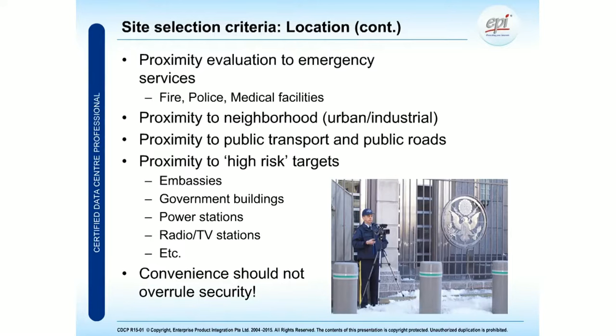Site selection is key. Also, proximity evaluation to emergency services. Should we be installing a data center next to a fire station, for example, or next to a medical facility? That could mean trouble as well. Proximity to the neighborhood, where people are living, an urban area - how about the sound of your diesel generator, or the noise of your cooling system on the rooftop? That might cause issues. And any proximity to high-risk targets, such as embassies, government buildings, television stations - we should keep an eye out and think about whether we want to install a data center close to those. So convenience should not overrule security. It might be quite easy to enter the building, but security is key.